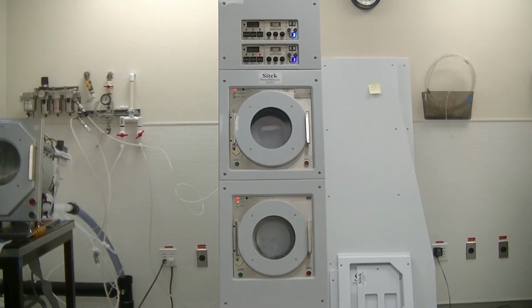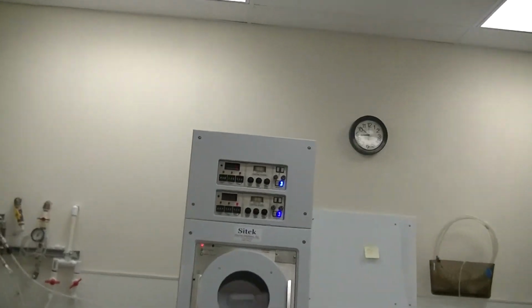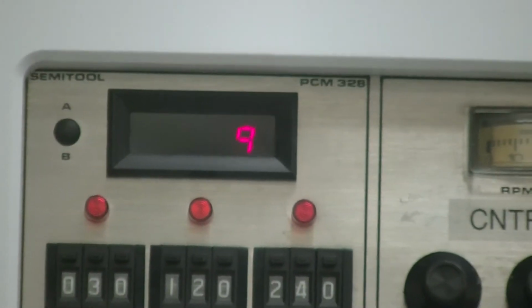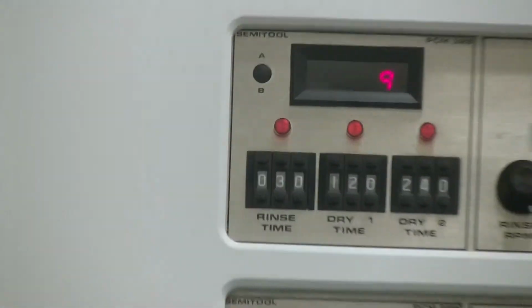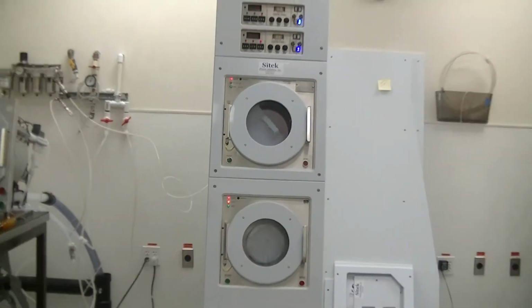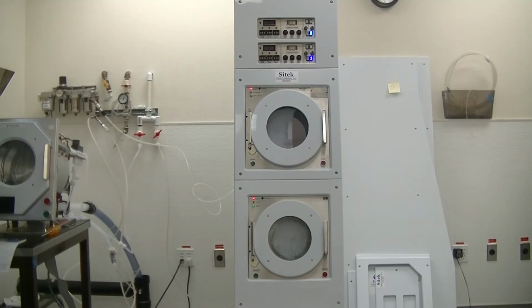Okay, we're finishing up here now. You'll notice that on the top here, we have a 9-second spin down, or an error code 9. That's not actually an error code per se. All that is a code that lets you know that the tool is still in its spin down delay. The spin down delay for these controllers has been set to 60 seconds.